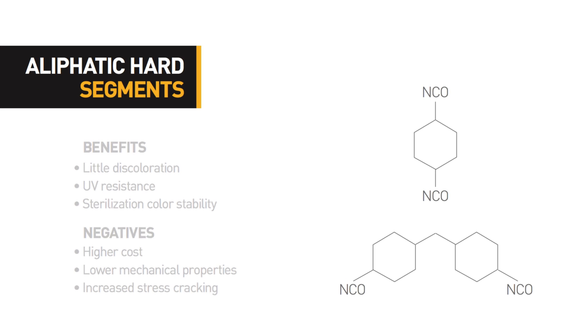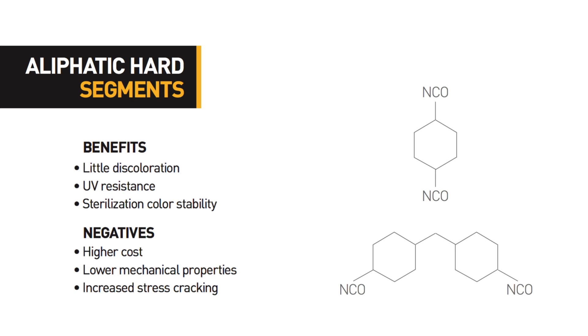The aliphatic diisocyanates show improved features for medical devices as they are more stable in light and do not break down to carcinogenic compounds. However, aliphatic diisocyanates are more expensive than the aromatic diisocyanates and they produce a polymer with lower mechanical properties. The loss of mechanical properties is slight and is most often accounted for in the device design. Additionally, the aliphatic urethanes are more prone to degradation by environmental stress cracking than the aromatic urethanes.